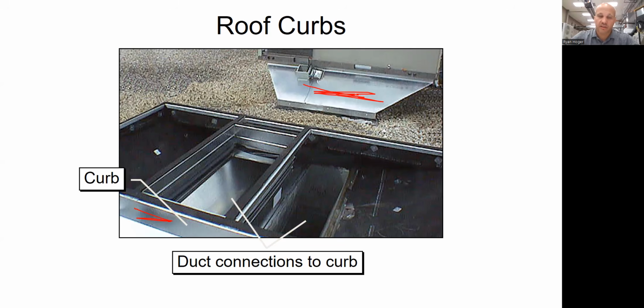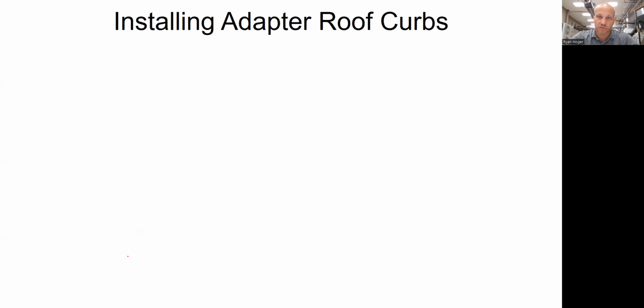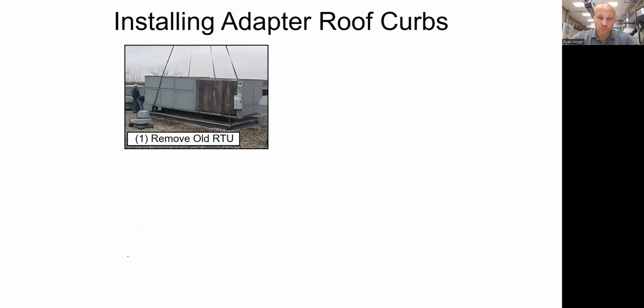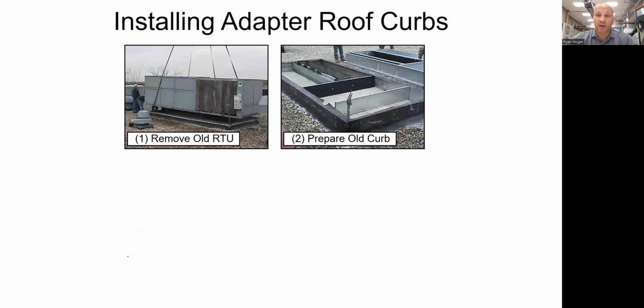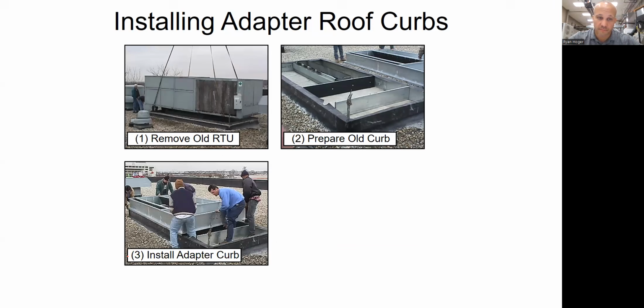I'll show you some pictures of it. So you might get a curb adapter. You can usually do that, but not always, but usually you could. So when you have one of these adapters, you lift the old unit off the roof with a crane, obviously. Unless it's really small, then maybe you can manually lift it, which we do sometimes. But usually there's a crane involved. Lift the old unit off, especially for one that size. You prepare the old curb, which means you clean off all the debris. There's probably adhesive and tape and stuff like that on there. You scrape all that crap off, so it's just the bare metal sticking out.